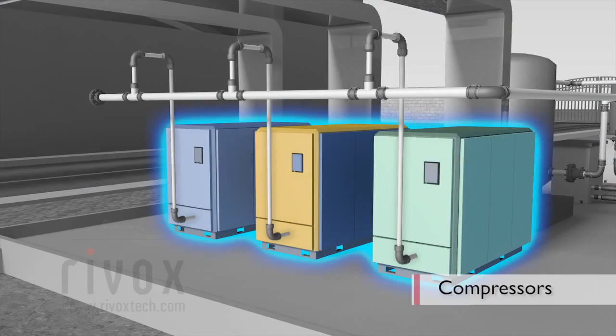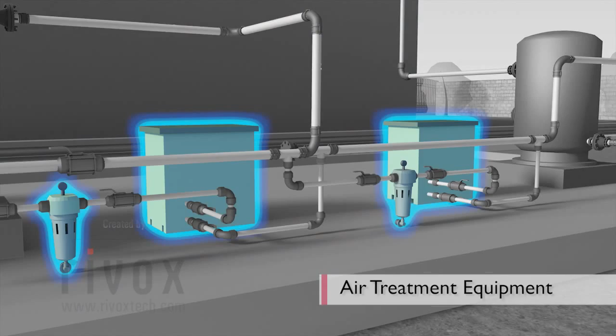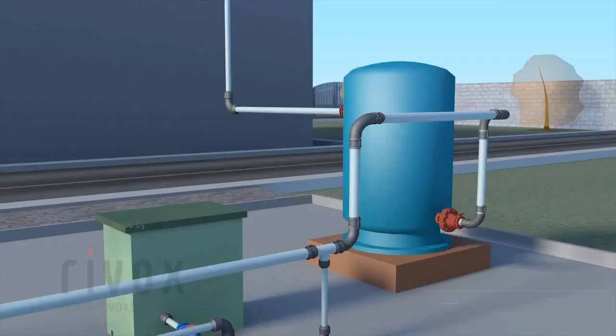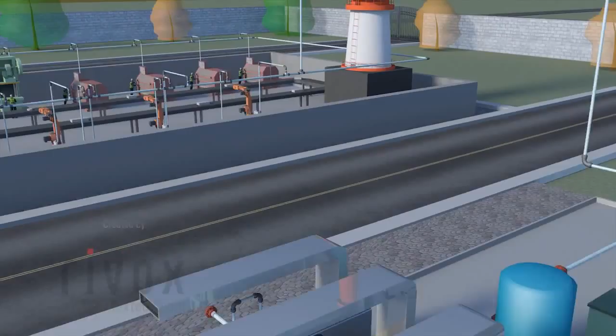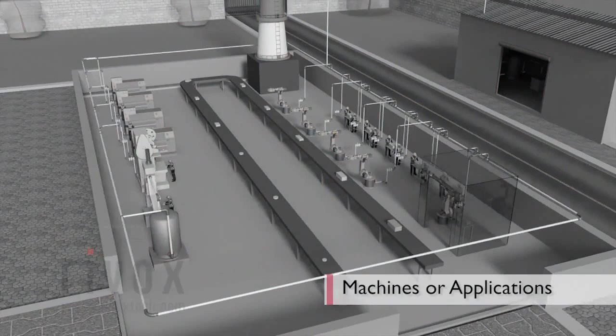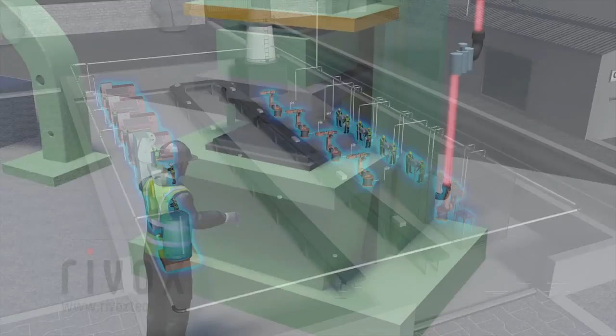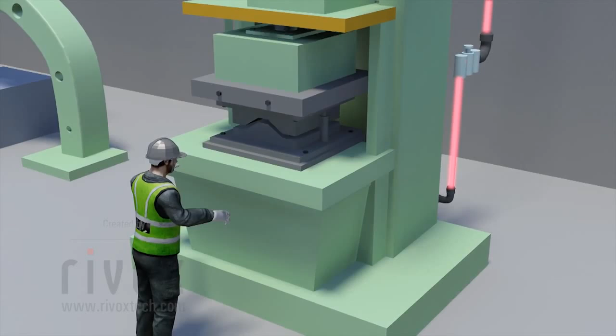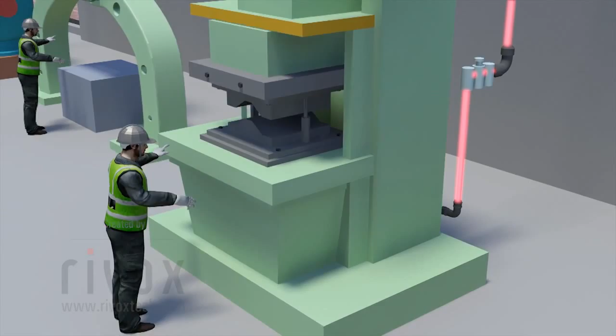Consider a typical compressed air network consisting of compressors, wet receivers, air treatment equipment, dry receivers, air distribution systems, and machines or applications where compressed air is consumed. When there is a sudden air demand due to starting of pneumatic equipment or tool, the pressure at that consumption point drops low. Since this consumption point is away from the compressor station, the compressor will notice this pressure drop only when this low pressure signal travels upstream through the distribution pipelines, main headers, air treatment equipment, receiver storage tanks, and finally reaches the compressor.